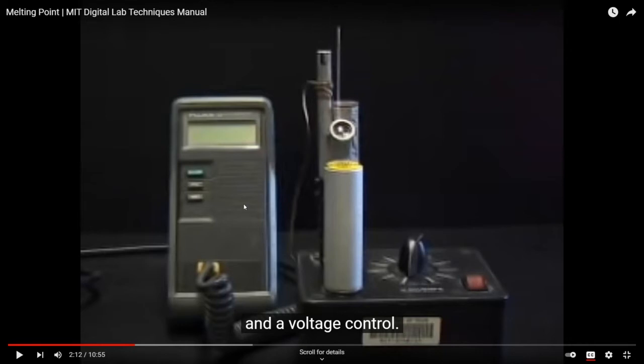But before COVID, we did not have many units with this digital recorder. But this one is connected to the digital thermometer, inserted to this slot instead of the glass thermometer. So make sure if you ever have a unit attached to this, the sensor is actually inserted. Otherwise, this is not reading the actual temperature, but it's going to read the room temperature.